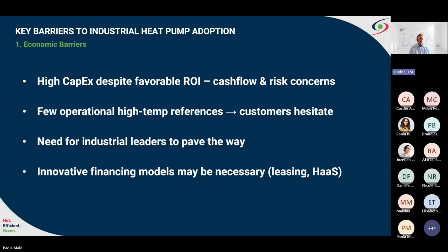Technically, installing a high temperature heat pump is more complex than replacing a gas boiler. Whereas a boiler is largely plug and play, heat pumps often require a source of waste heat or heat sink integration, which must be engineered case by case. Heat pumps do need a heat source, and sometimes that source isn't available, or it's at a very low temperature, which results in high temperature lifts and thereby also lower COPs.